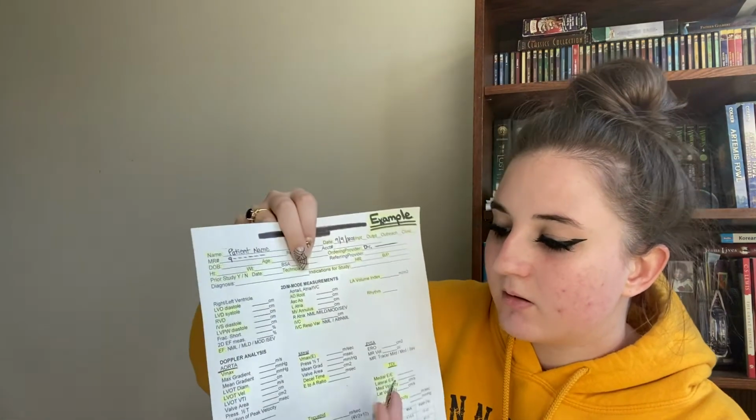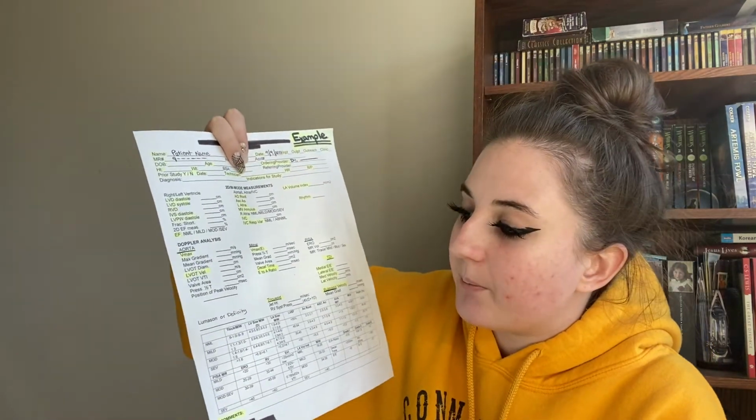Also, lastly, if you used contrast, I mean, it's not really contrast, I don't know how to describe it. We use Lumason a decent amount. I wouldn't say a lot, but a decent amount on people, because the bigger you are, the harder you're going to be able to see it, because there's just a lot more space to go through to get to the heart and come back. So obviously, if you take physics, you lose signal. So you would put whether you used Lumason or Definity down here. So that's everything for the numbers.